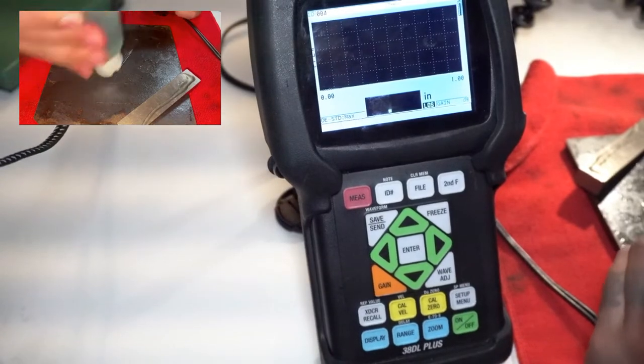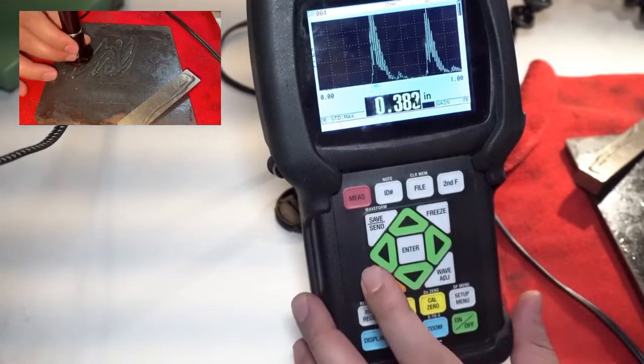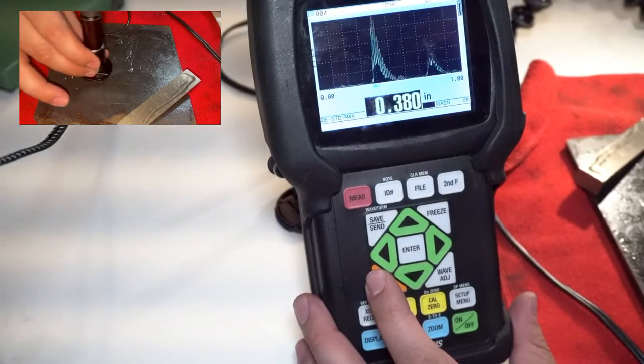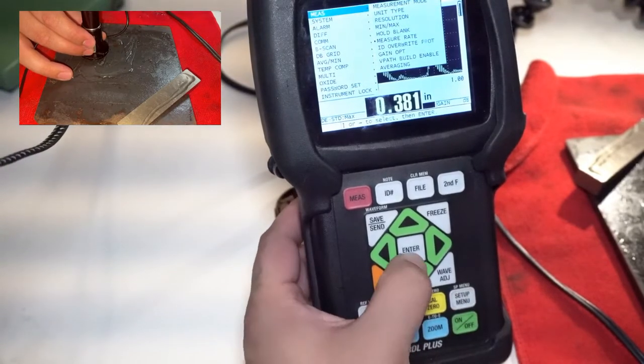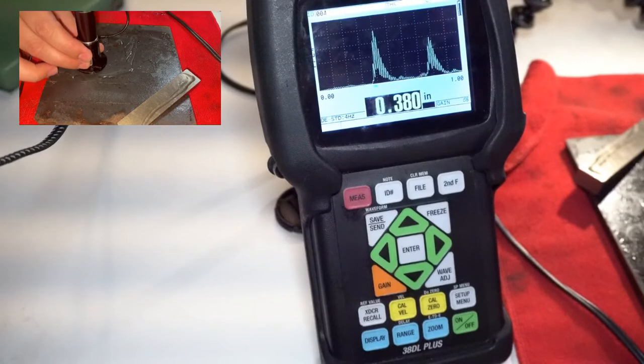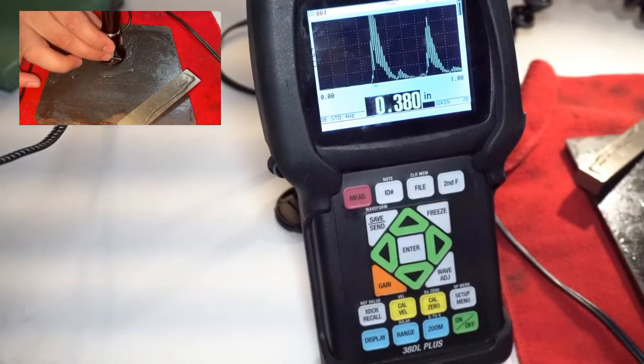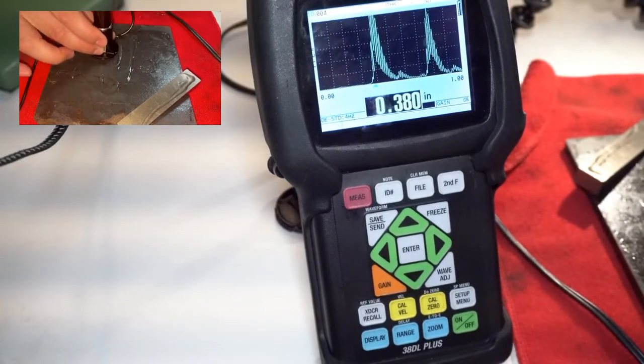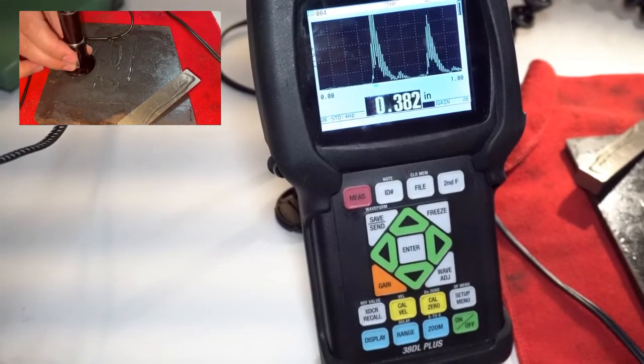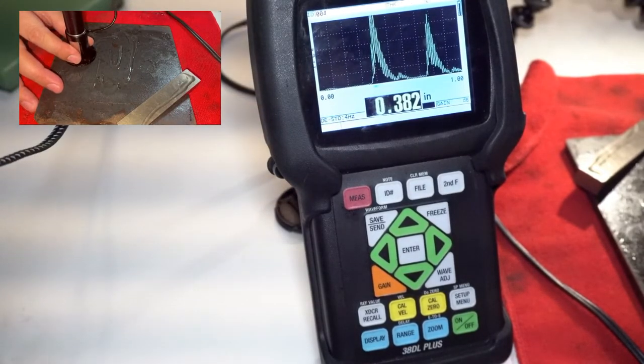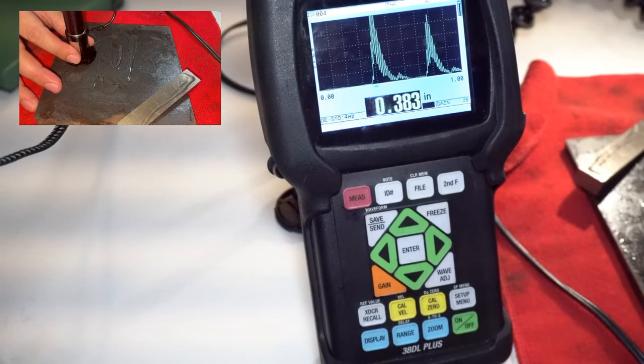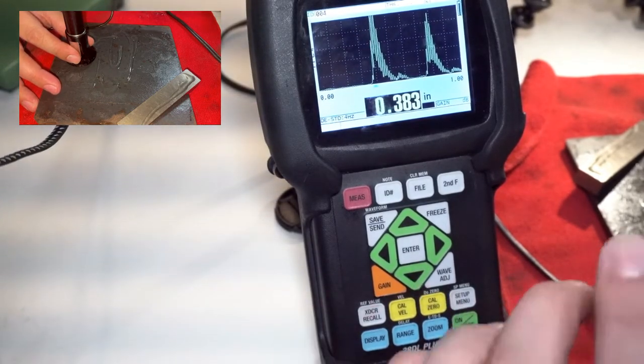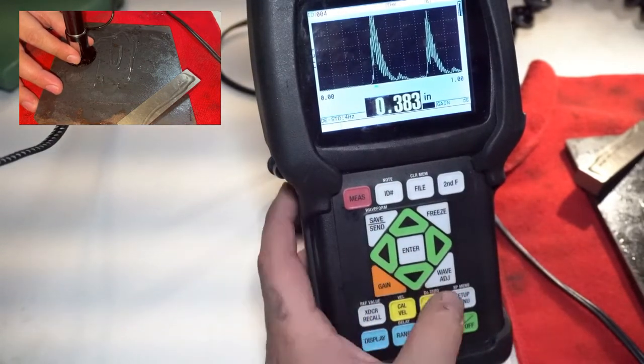Put a little bit more couplant. You can never have enough couplant, right? I'm kidding. Signals move pretty quick. Now in comparison, move down to 4 Hertz. You can see the signals don't move as fast. I've changed still about the same kind of scan speed, but definitely not seeing as fast of a movement from the signals as we were previously. Again, this is something to keep in consideration when you're trying to find the thinnest area of a pit or a pitted area, the thinnest or the lowest numerical value of a pitted area.